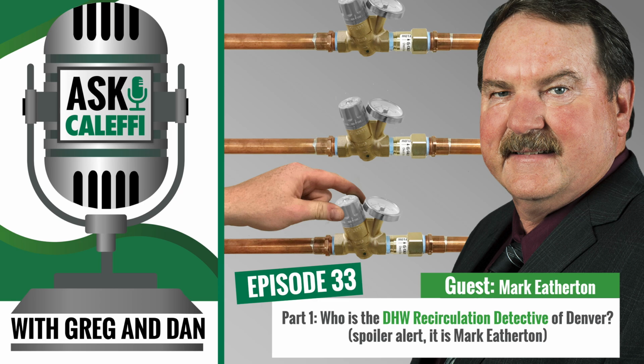I had a call this last week from one of our manufacturer reps, and he says they've got a prison that they are unable to get hot water to their showers. He said all the showers in one place, but I think I may have discovered what it is, because he had attended one of the Caleffi seminars that I had spoken at. And he said they've got all of these mop sinks that have a chemical mixing station on them, where the hot and the cold water come together to a common point, mixed down, goes through, picks up soap, goes into the bucket.